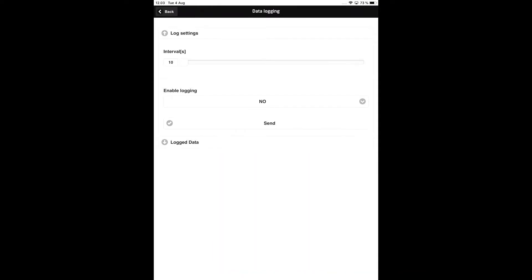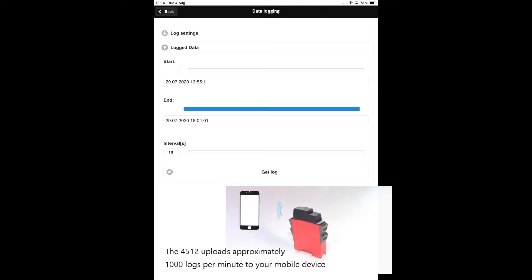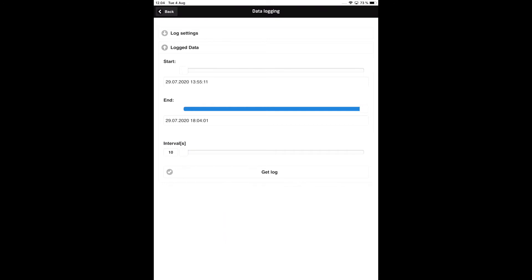Tap the logged data button to select what data is uploaded to your mobile device. Because the 4512 communicates via Bluetooth, the upload rate is approximately 1000 logs per minute. This means the upload time can be long for large log files. You can reduce the upload time by moving the start time and end time sliders to upload only the part of the data log that you are interested in viewing.